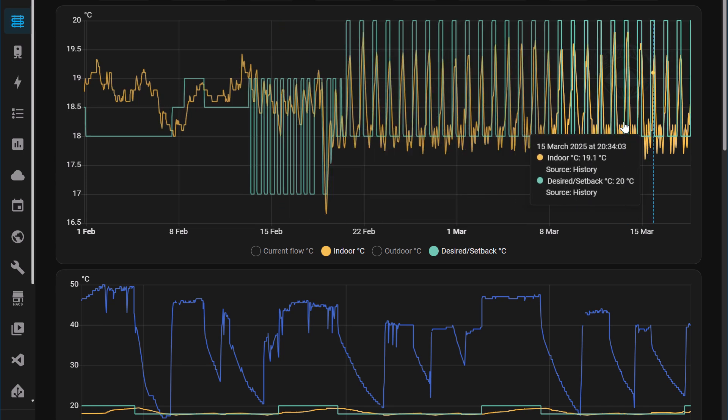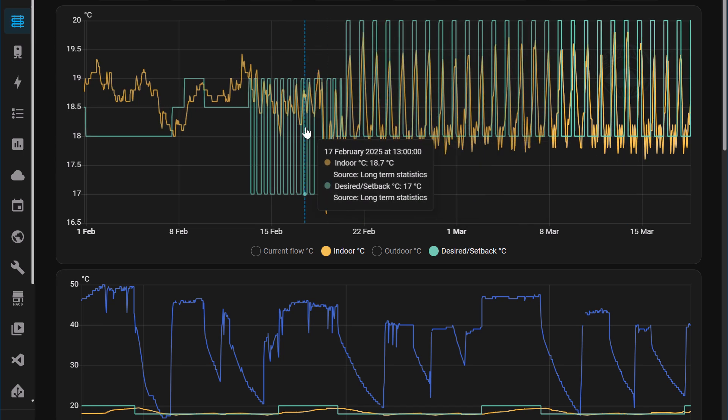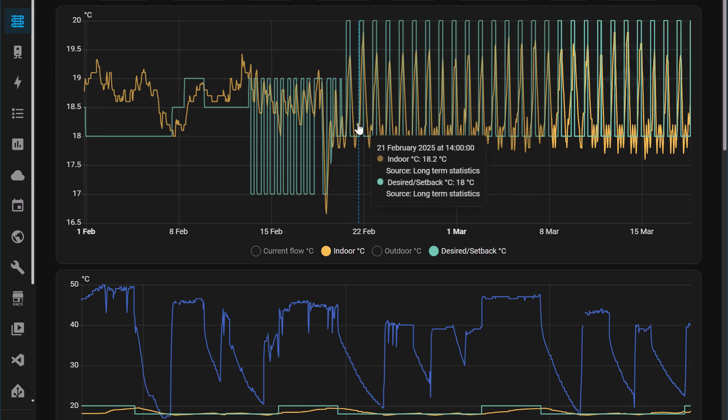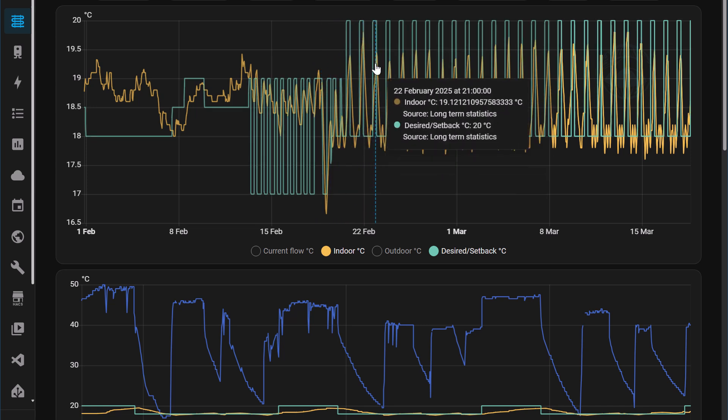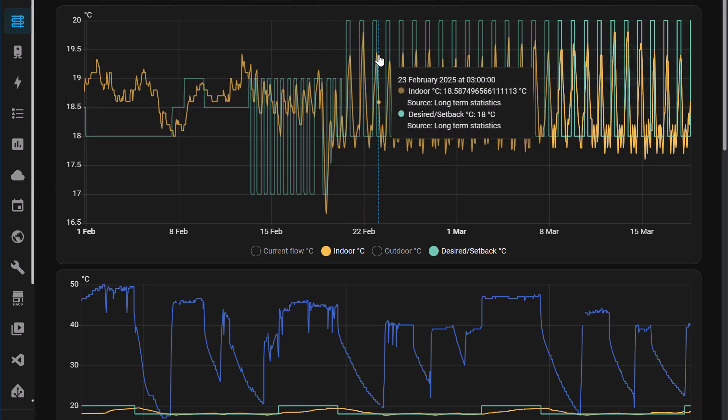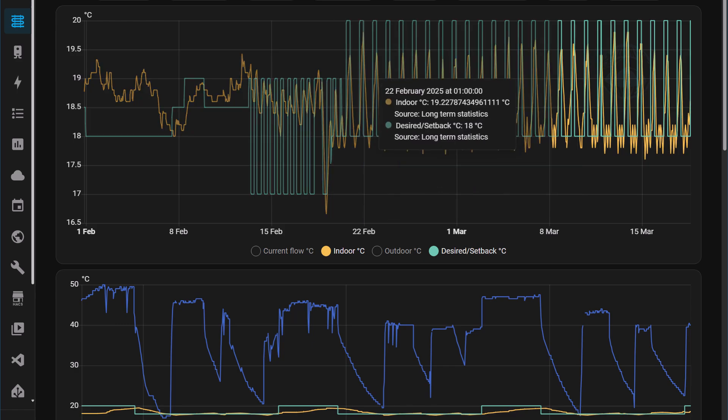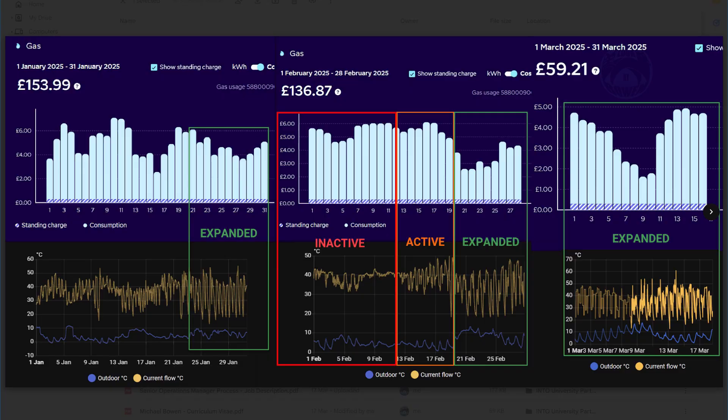This has been absolutely the resolution, I should say. Room temperature mod set to expanded. And I've got a heat curve of 1.3. And what it has done, it's shown me here is where I turned on expanded. You can see that the gas bills are a lot lower than what they were in the first 19 days of February. Now, I will say again, if you look at the temperatures from the 21st of February till end of the month, they were a lot higher than they were in the first part of February.